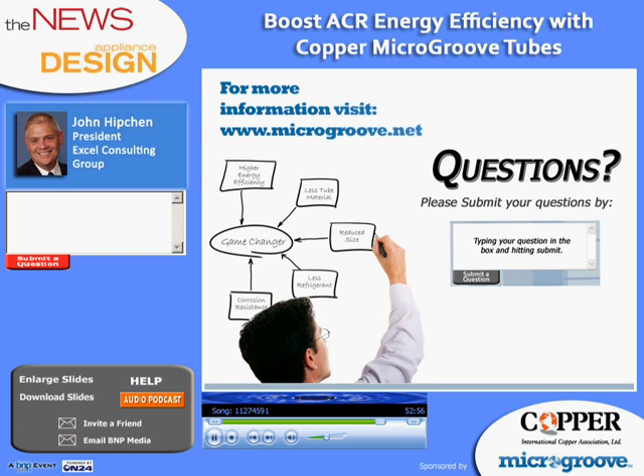The quick answer to that is yes. I do not recall a study with any particular refrigerant that did not show some sort of enhanced heat transfer with the MicroGroove tube. And again, the reason for that is because of the boundary layers that are reduced with the MicroGroove tube. Doesn't matter what refrigerant you've got or what media you're using, when you reduce those boundary layers, you're going to get better heat transfer.